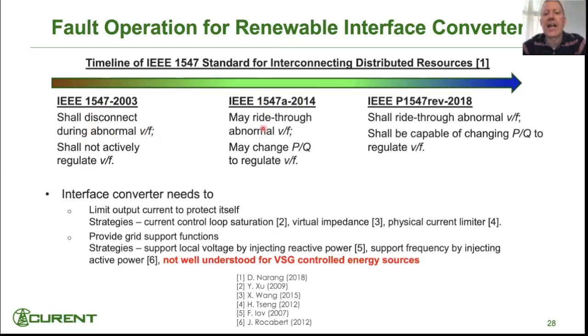About a decade later, they changed it from 'shall disconnect' to 'may ride through,' meaning you didn't have to disconnect and it was okay to hang in there. Just a few years after that, they went from 'may ride through' to 'shall ride through.' As the renewable percentage got higher, they found they couldn't just tell generators to disconnect, since it would make things worse. They had to hang in there and help out.